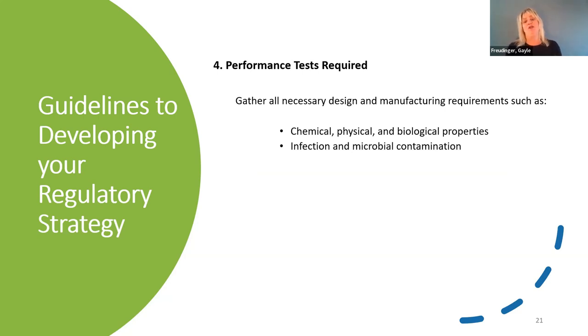Many commonly used medical devices such as catheters, cardiopulmonary bypass systems, and so forth, anything that comes in contact with blood could have contamination. Therefore, these devices require an assessment for hemocompatibility, risks such as thrombosis prior to submitting to a regulatory agency for market approval. So you're going to need to do an assessment prior.